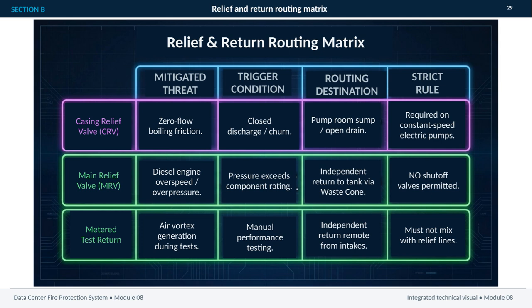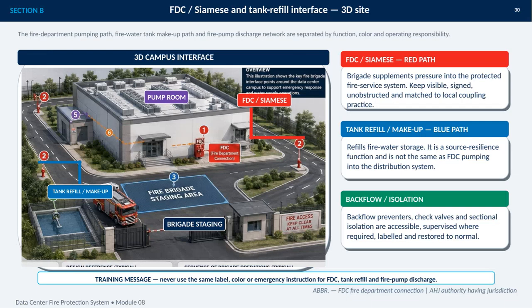The metered test return serves a different purpose. It manages air vortex generation during manual performance testing, and the return must be routed independently, remote from the intakes. It also must not be mixed with relief lines. Together, these rules prevent incompatible flows from sharing a route and make sure each relief or testing condition has a controlled destination.